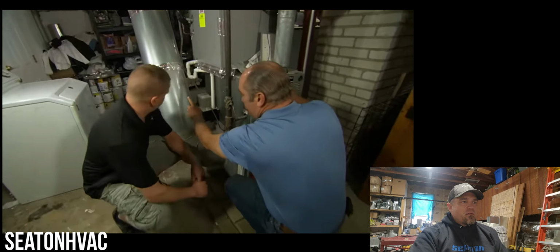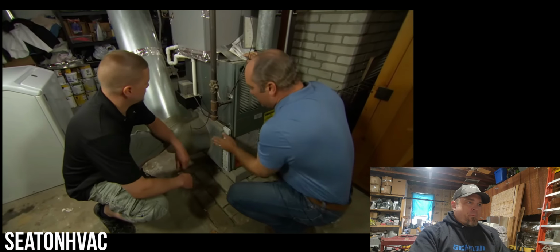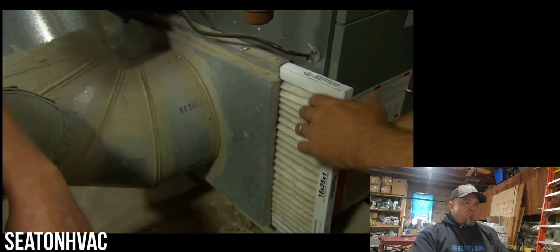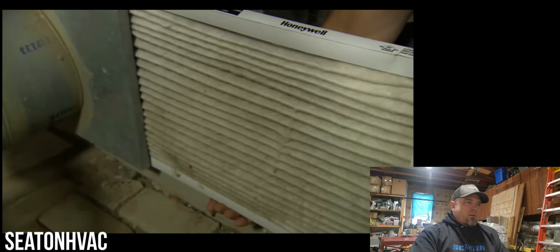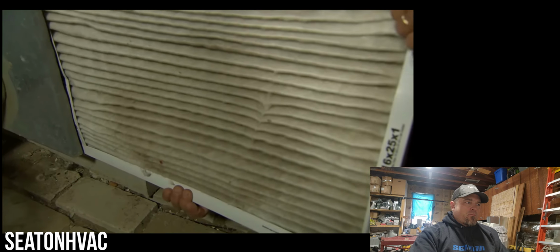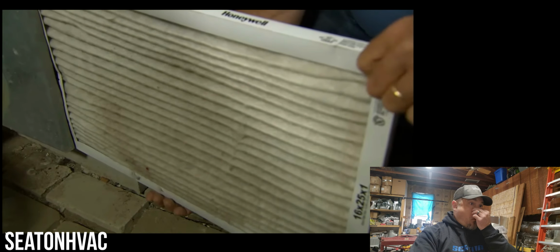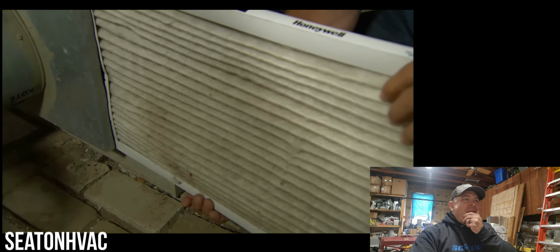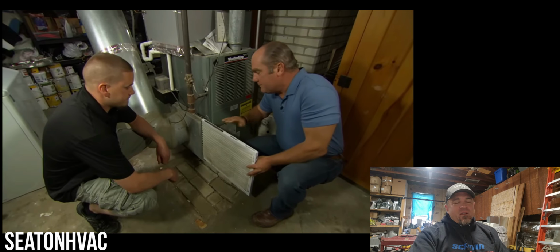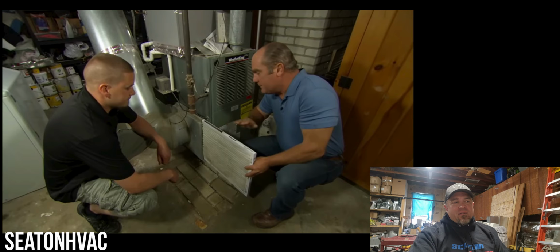On anybody's furnace or AC unit, there's got to be some sort of filter like this. So this is a return air filter, and this thing is relatively simple, but it's got to be clean. Now that isn't perfectly clean, but it's not terrible. You change this? All the time. Okay. See just that round dirt ring on that filter. So it's only filtering through that, the way they tap that in. It's not dispersing across the filter properly. That's not what you want.